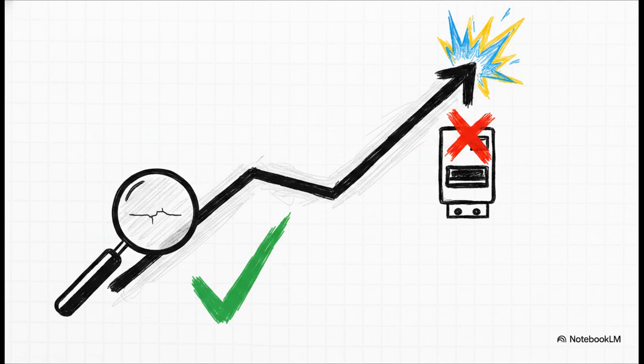Reading that dashboard trend catches early insulation degradation months, and I mean months, before a static alarm or a protection relay ever sees it. By tracking those changes under a flat load, you're fundamentally shifting from just reacting to a failure to proactively extending the transformer's life.